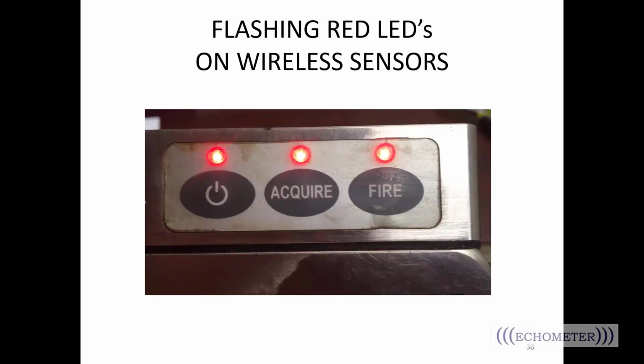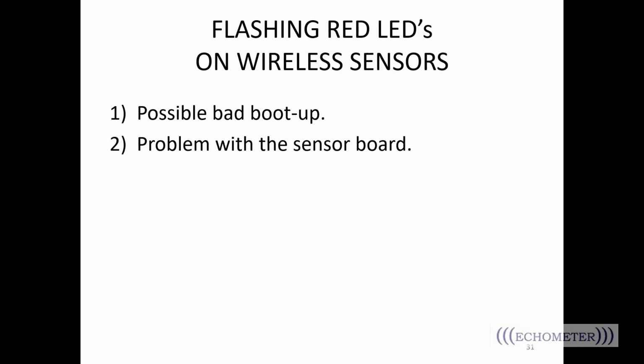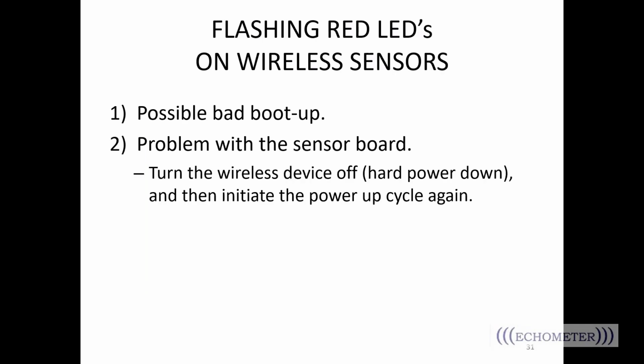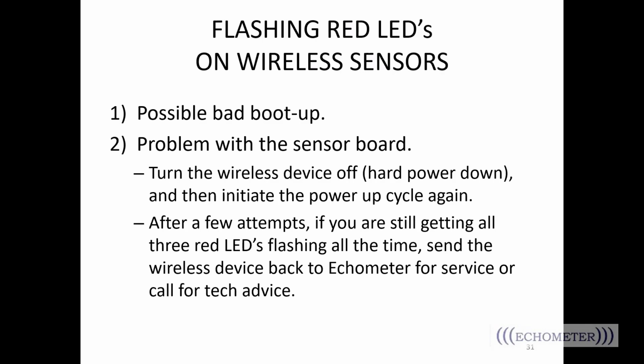Flashing red LEDs on the wireless sensor means that there's a problem. A lot of times you'll see this happen at boot up, right? You'll turn it on and you'll see the red lights flashing. So probably it's a bad boot up or a problem with the sensor board. So we suggest you do a hard power down. Hold that power button down for 8 to 10 seconds and then initiate that power up cycle again.